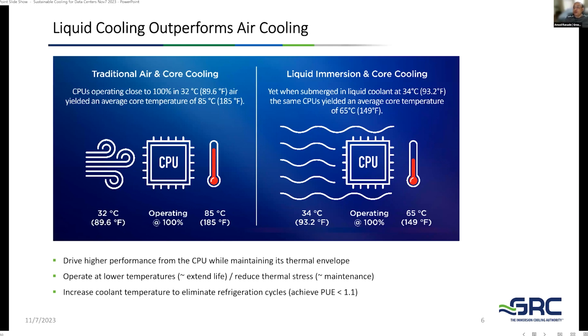Getting the chip to work more until it reaches that 85 degree temperature is one way of operating. What we are doing is getting more performance from the same chip. The second way to operate it is, okay, if I operate the chip at 65 degrees instead of 85, I am providing lesser thermal stress on the chip, which means the performance would be better, the life of the chip would be better, and so it will require lesser maintenance. So the reliability of the IT infrastructure improves if I just continue to operate at a lower temperature.